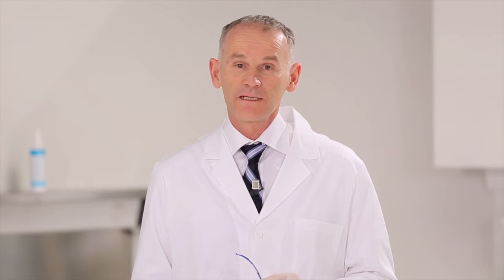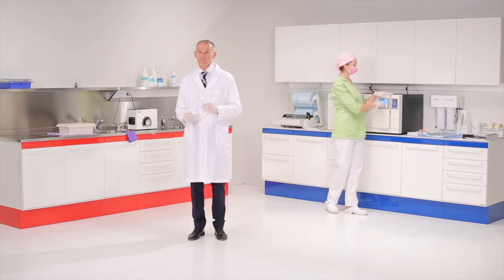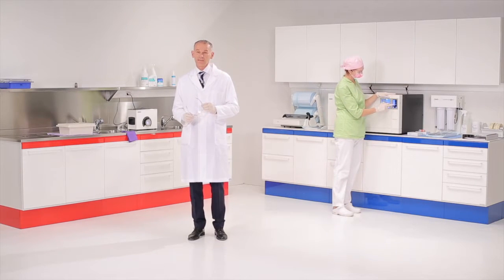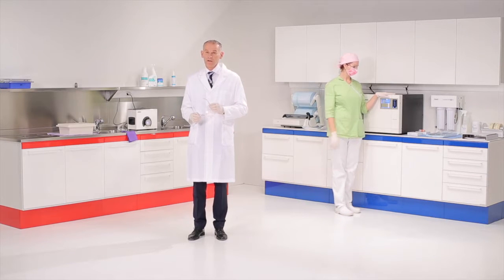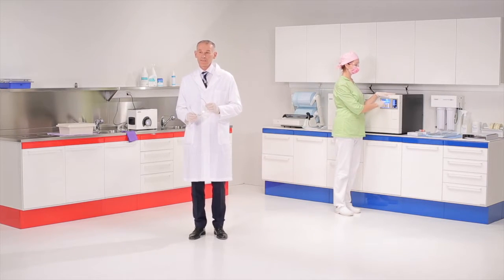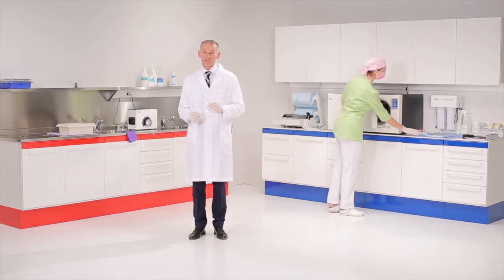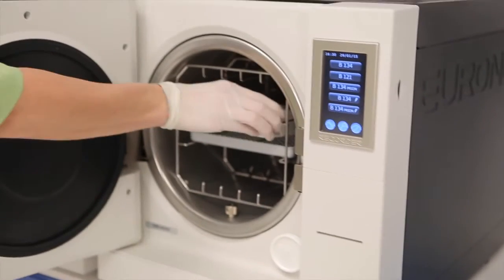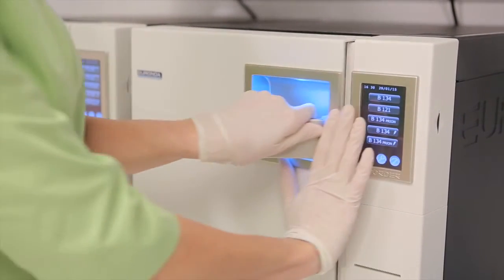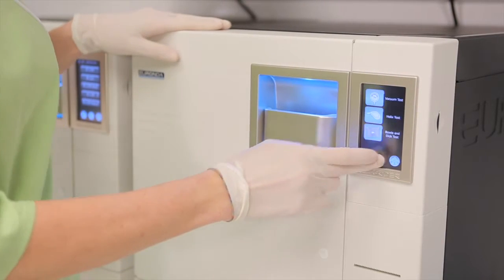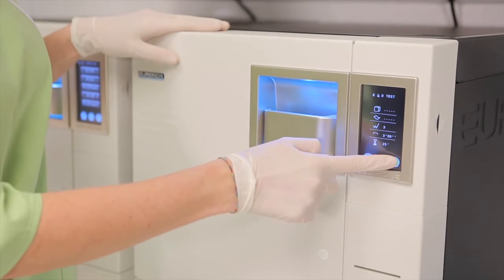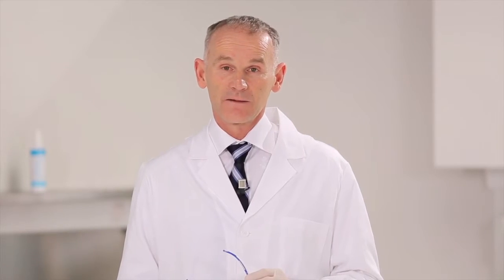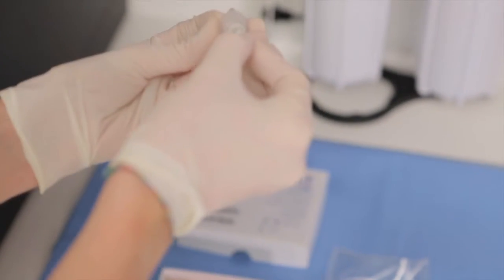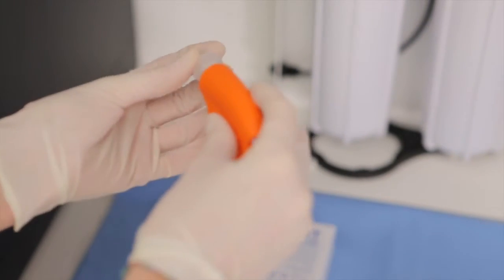Tests and periodic controls enable the proper operation of the autoclave to be checked. The vacuum test enables the integrity of the tanks and the seal of the vacuum indispensable for the sterilization to be checked. The Bowie and Dick test is carried out through an instantly recognizable command on the e-touch screen and enables the extent of penetration of the steam in the porous loads to be checked. The helix test is carried out through a specific cycle identified on the equipment and enables the extent of steam penetration in the hollow loads to be checked.